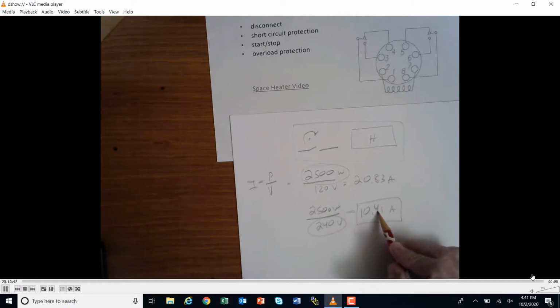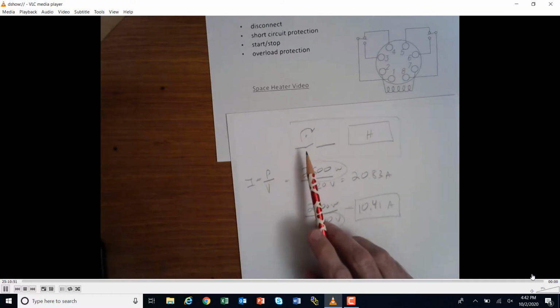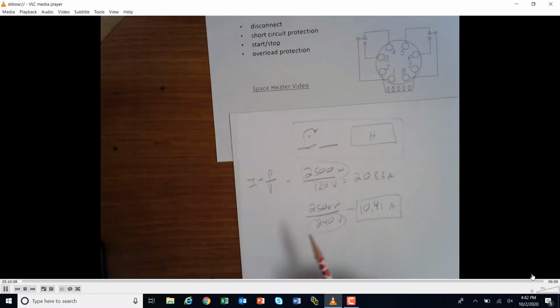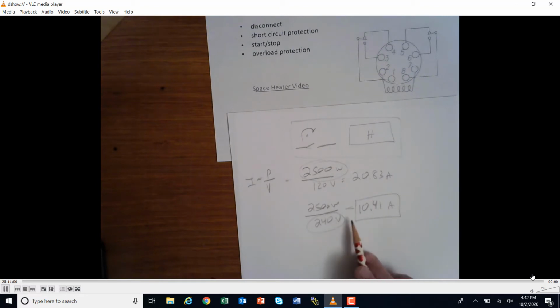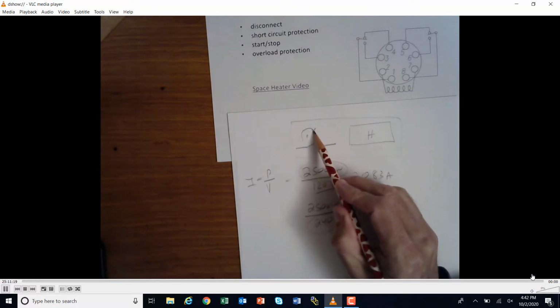The next issue was the timer switch — these little switches aren't really rated for high voltage or high amps. They're typically rated for 120 volts, and they certainly can't switch 20 amps; that would burn the timer contacts up. But I can't run 240 volts through it either, since it's not rated for that high voltage. So I couldn't just directly hook this timer in.